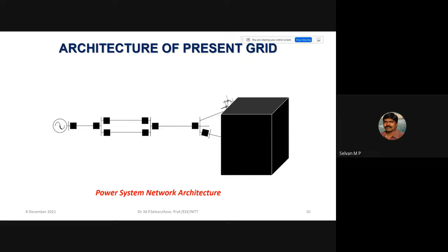which is very critical, so you need a very sophisticated protection system. If you look at the distribution network, they will have simple overcurrent protection. You will have fuses at many places. Every distribution transformer has only the fuse. And the distribution substation, you may have relays and circuit breakers. And we have manually operated disconnect switches. You might have seen near the DT, distribution transformer, we have manually operated disconnect switches. This is what the scenario, right?